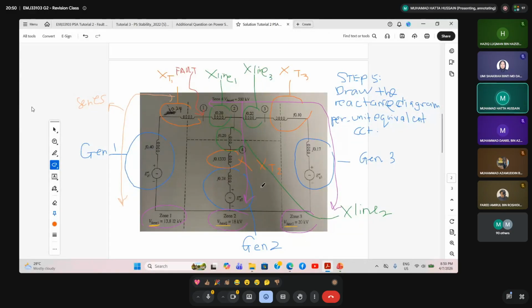Then we have transformer 3, connected from bus 3 going to the ground. At bus 3, for transformer 3, we have the reactance value, and we also have generator 3, meaning voltage source in series with the reactance of generator 3. This is how we draw the per unit equivalent circuit or the reactance diagram.